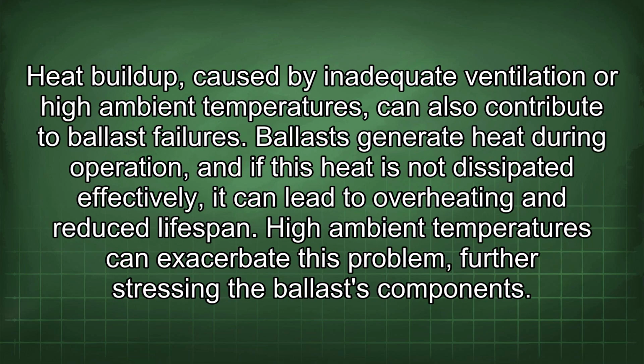Heat buildup, caused by inadequate ventilation or high ambient temperatures, can also contribute to ballast failures. Ballasts generate heat during operation, and if this heat is not dissipated effectively, it can lead to overheating and reduced lifespan. High ambient temperatures can exacerbate this problem, further stressing the ballast components.